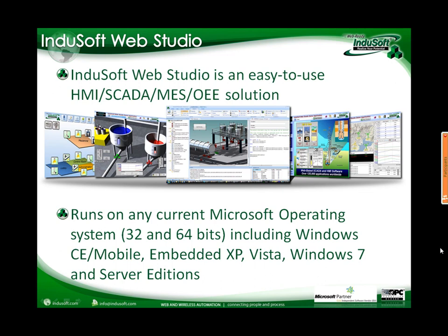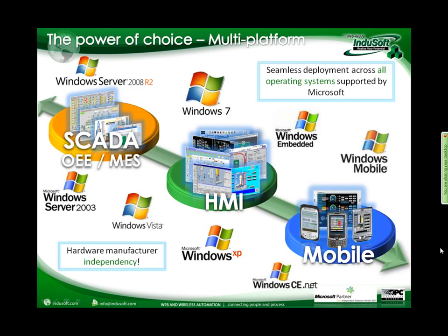InduSoft Web Studio includes a built-in protocol analyzer to monitor PLC communication, and supports online configuration — you can run the application on the machine and make changes from a remote computer; when you save and download changes to the runtime station, the changes take effect on the fly without shutting down the machine. All applications can be deployed on any Microsoft platform, from Windows Mobile and Windows CE to Windows Embedded, Windows 7, and Windows 2003/2008 Server, both 32 and 64-bit.